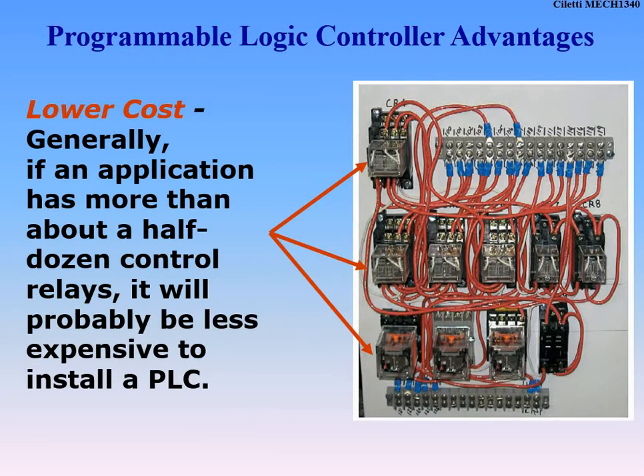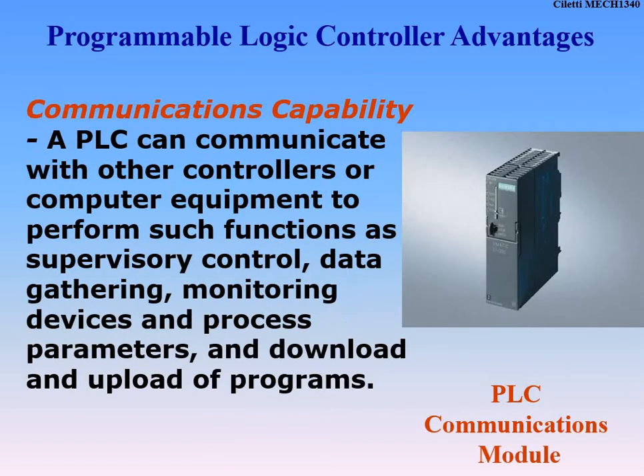Lower cost in the long run. It's very expensive to have to wire up a bunch of relays because you have to pay someone to wire all of these up. There's more trouble with maintenance too — look at how many different wires go into different relays. If it's a smaller application — maybe half a dozen controls — then relay logic makes sense. It's not effective to buy a PLC for that. But anything greater than that, it's much more effective to buy a PLC, and you never have to rewire anything — it's all about changing your program.